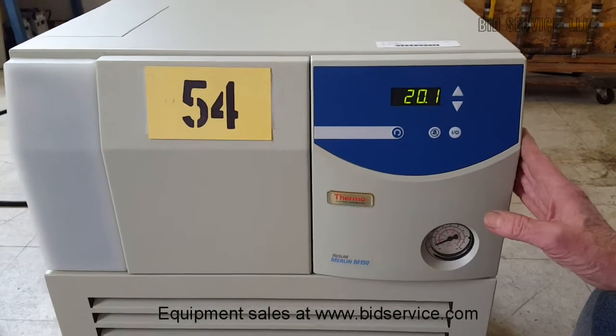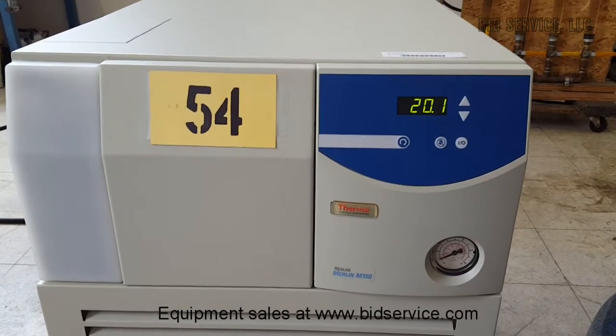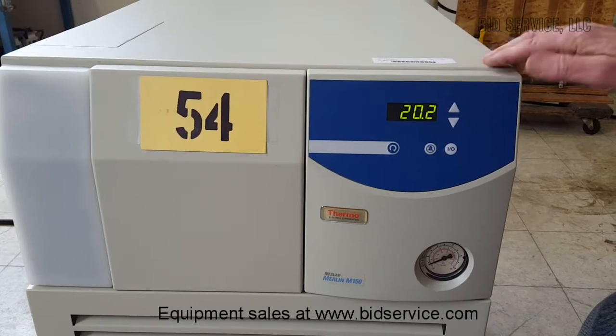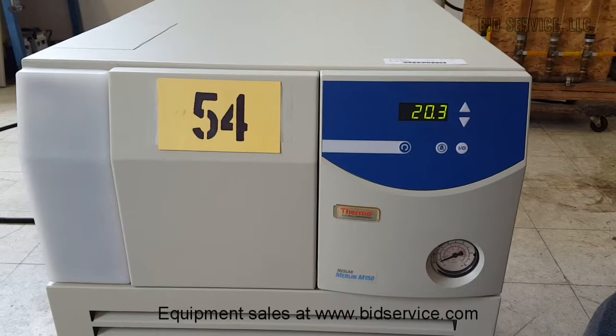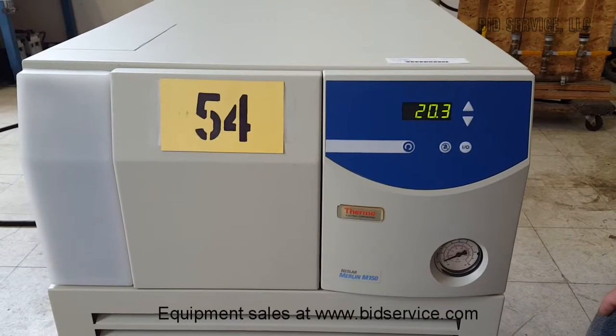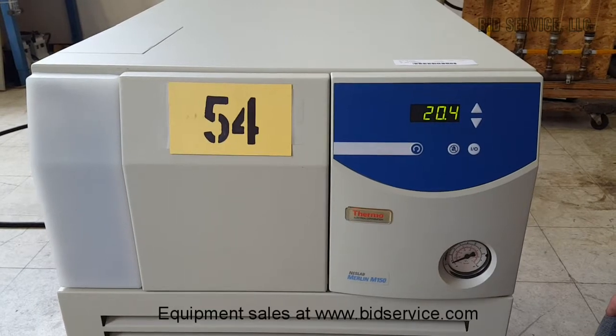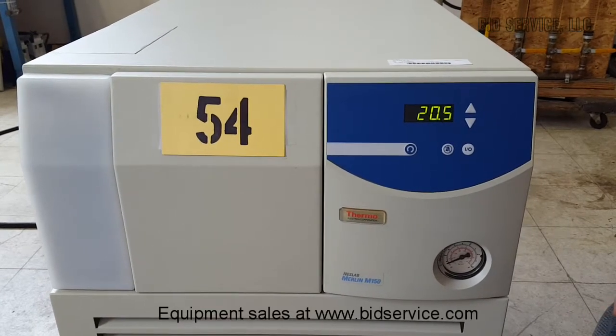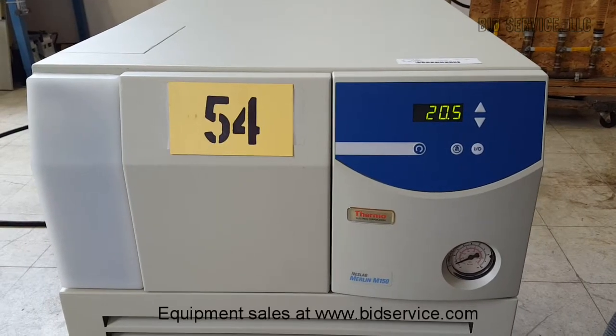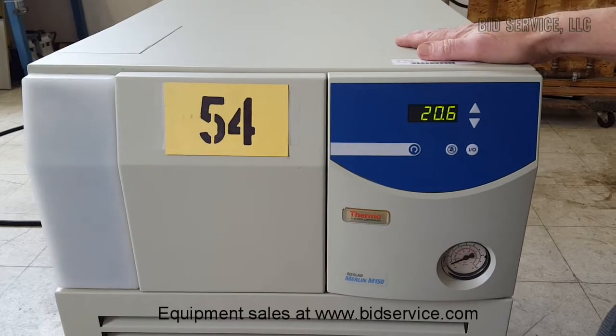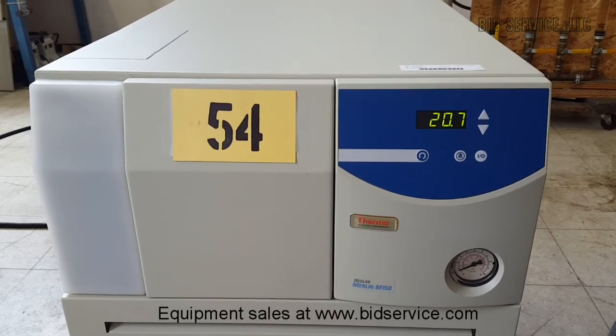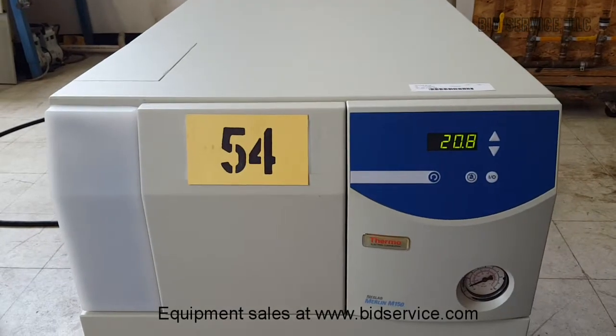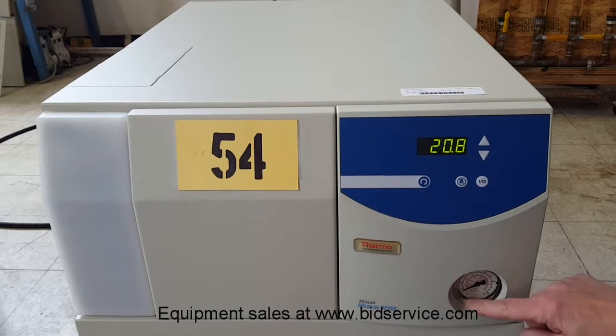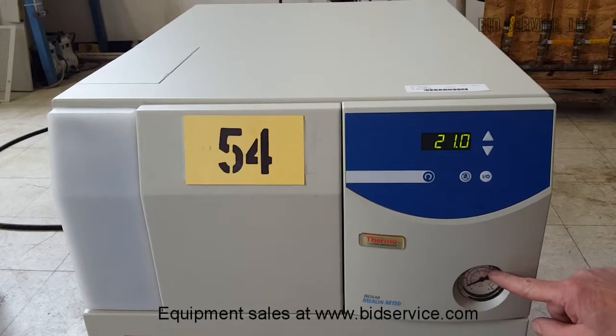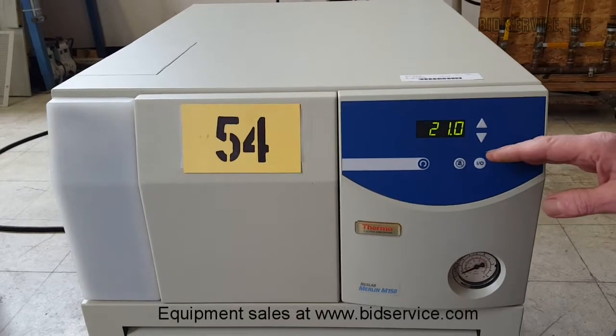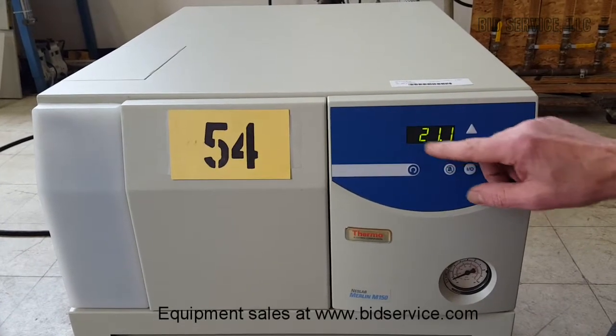Some other nice features about this controller: if the reservoir runs too low, it will turn off the system and sound an alarm, signaling you to fill up your reservoir. It also has a pressure sensor, so that if the line gets plugged down the line, or in many cases where these are running out into the actual clean room floor, if debris should plug it up, instead of just sitting there cranking, once the pressure gets too high it will shut down, sound an alarm, and show a signal that says high pressure.